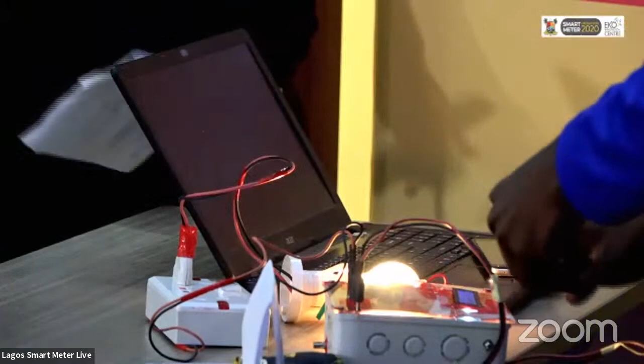Just for the purpose of this gathering, I'd like to give a bit of enlightenment about cost consideration when it comes to metering. There are about 5 classes of metering in the sector today: 0.2, 0.5, class 1, class 2, and class 3. These are part of the component requirement in selecting your components, because the sensitivity of the component is proportionate to how sensitive you want your meter to be in terms of accuracy.